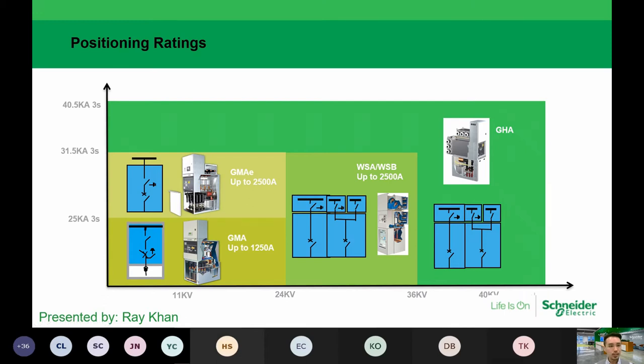Okay, so over here comes a very interesting chart that talks about the positioning and rating of the switchgear. If I start with the x-axis, that is the portion, all right? It focuses on the kV rating, from 11 kV all the way up to 40 kV. So you can see the progression in here.